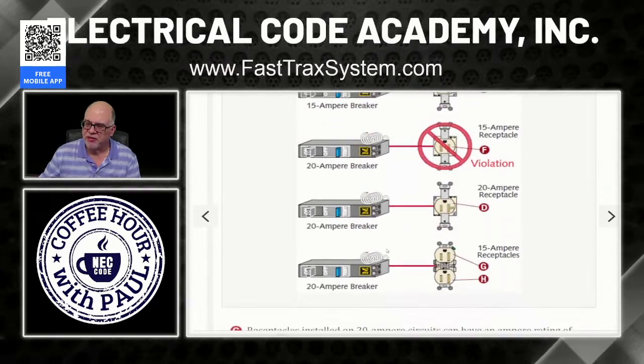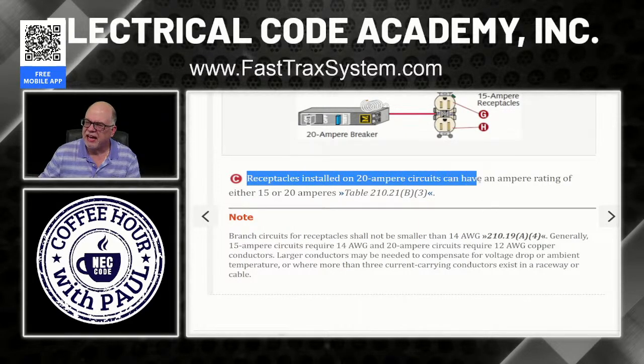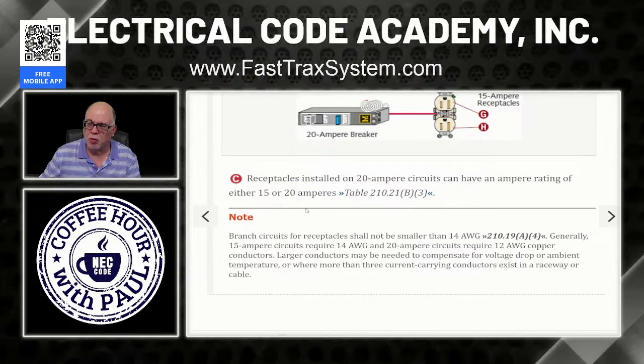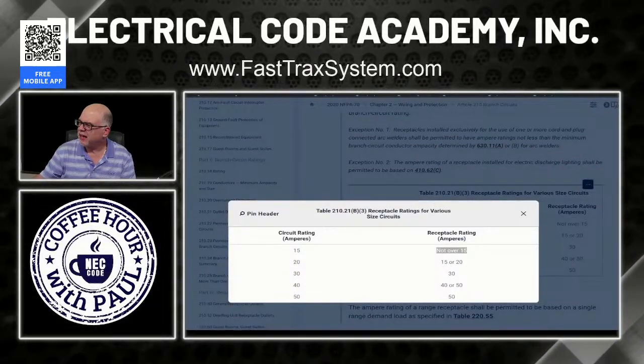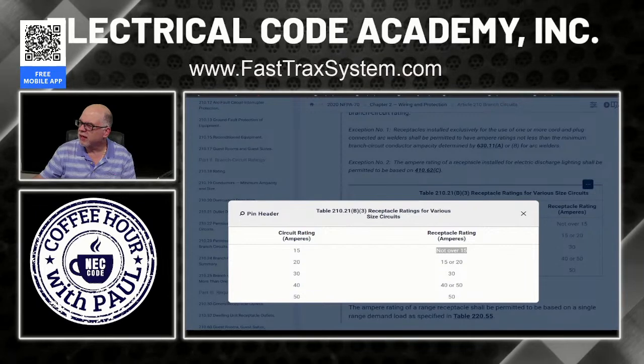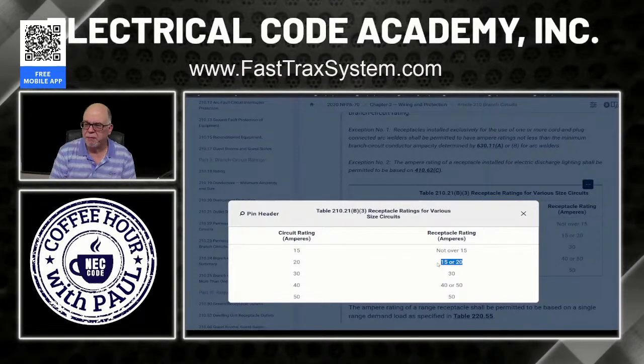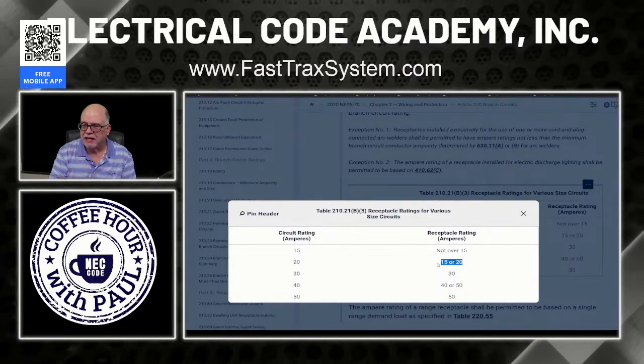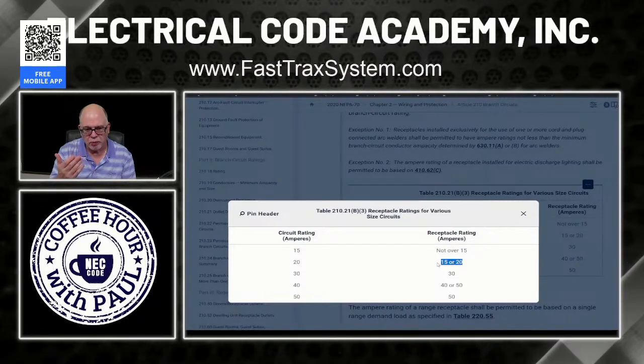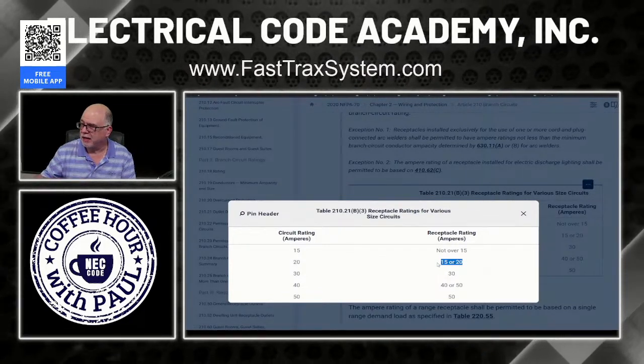Now, we'll go down and read C real quick. So here, it says, receptacles installed on a 20-amp circuit can have an ampere rating of either 15 or 20. And that's what it says in Table 210.21(B)(3). So we'll go look and verify that. Well, here we are. And it looks like right here we see 20 amp circuit, and it says 15 or 20 right there. So if it's a 20 amp branch circuit, I can use a 15. Now, me and you both know that the internal guts are exactly the same, right? But that is just exactly what code tells us that we can do. And you can argue the semantics if you want, but at the end of the day, it is what it is. And you have to respect it.